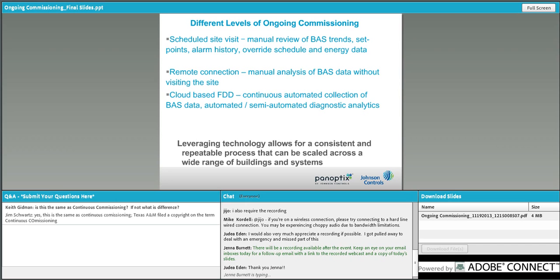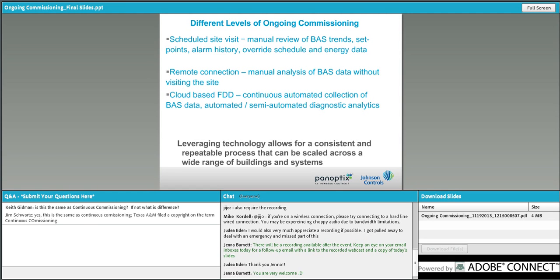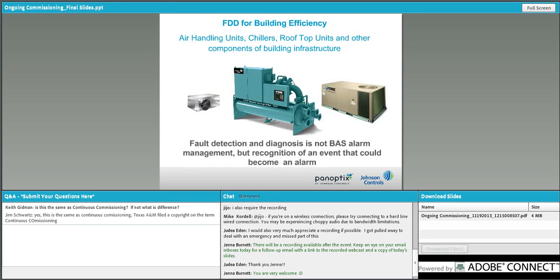Fault detection is the recognition of undesirable abnormalities occurring in equipment and systems in a building, and fault diagnostics is the isolation of the root cause of the problem. So with FDD, everything is a question and answer scenario. The detection and diagnostic process is automated by software, asking a rules-based question and running data from control points through algorithms to detect and then diagnose the fault. Actually, the detection is much easier to achieve than the actual diagnostics, for lots of reasons. Think of going to the doctor: they can tell that you have high blood pressure, but that's the detection. Diagnosing what's causing it is a whole other process.